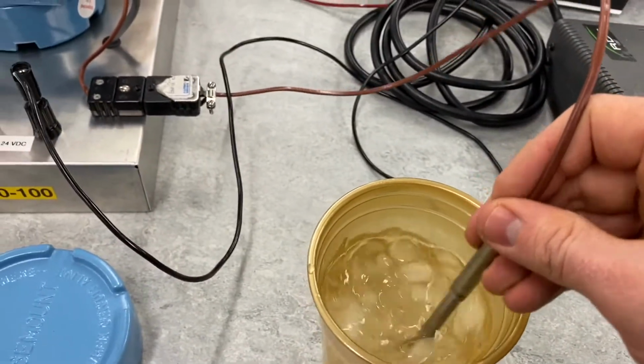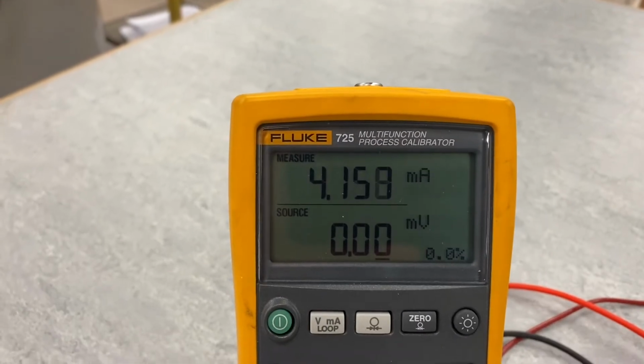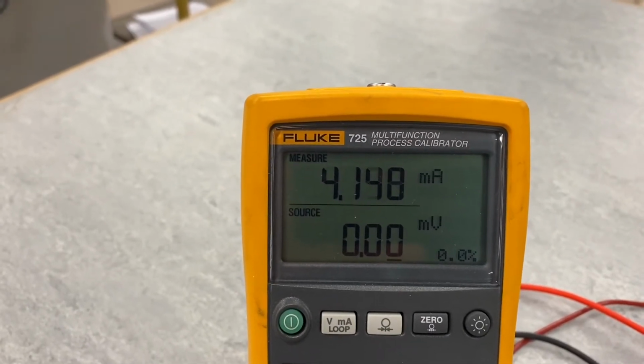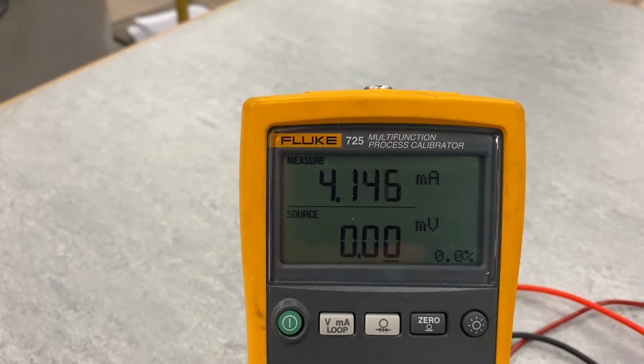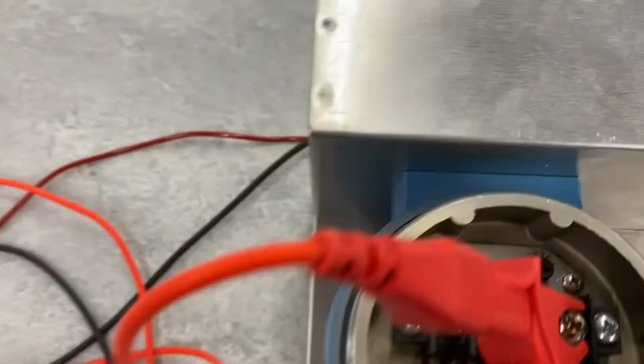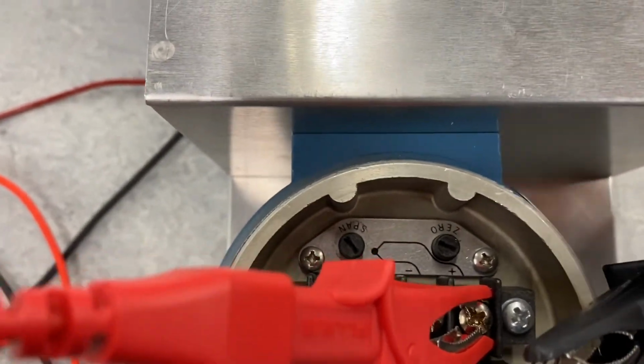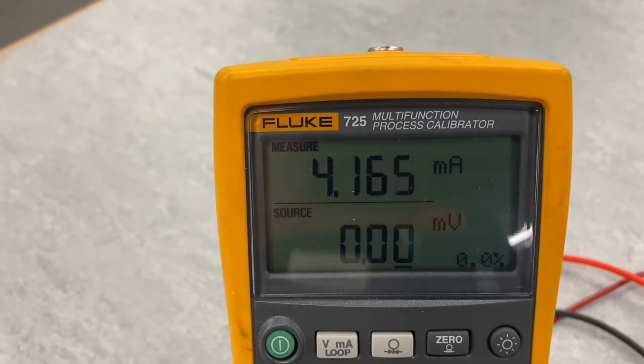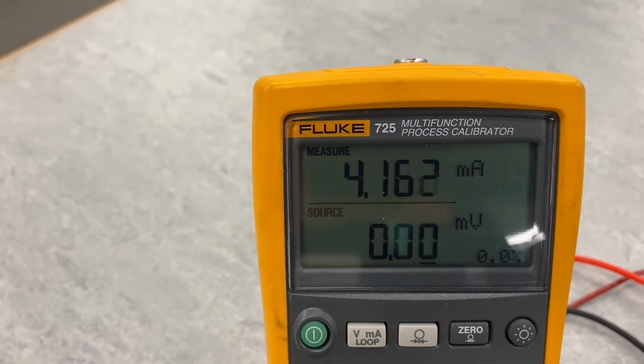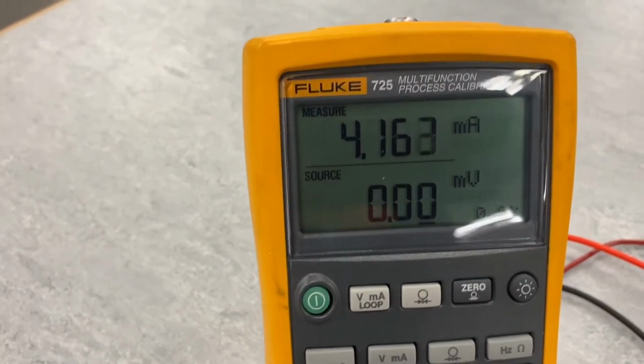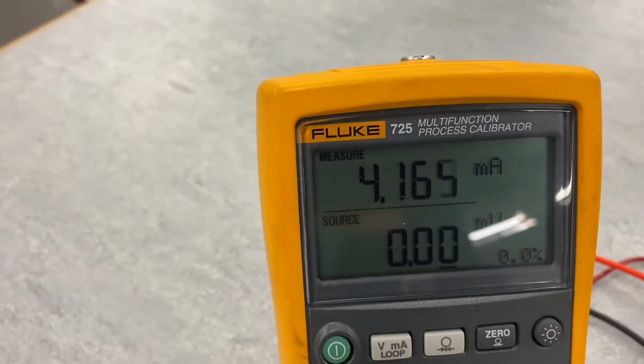So right now, if we are sourcing with the ice bath method here, as long as we're agitating our ice bath and we're sourcing 0 millivolts, then our transmitter should be reading 4 milliamps. To make that adjustment, we would go to the top side of our transmitter here and adjust this zero screw until this reads 4 milliamps. To do our span, or to set it for 20 milliamps, we're going to be adjusting the span setting here. The next thing we need to figure out is what voltage to source to represent our span.